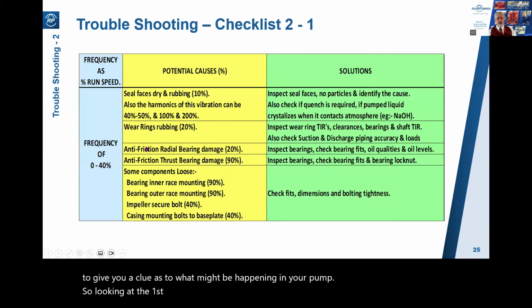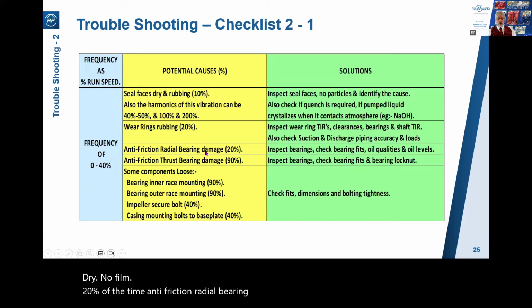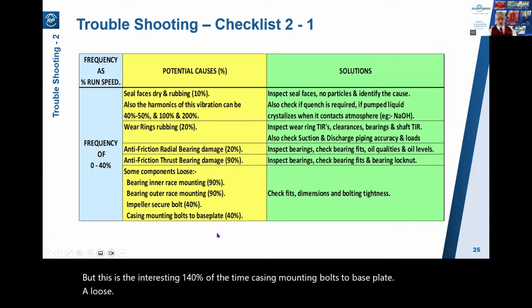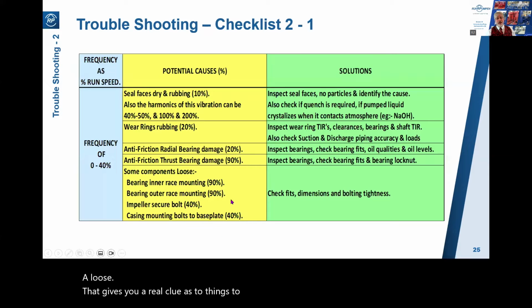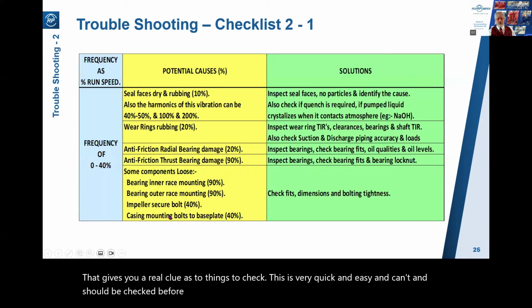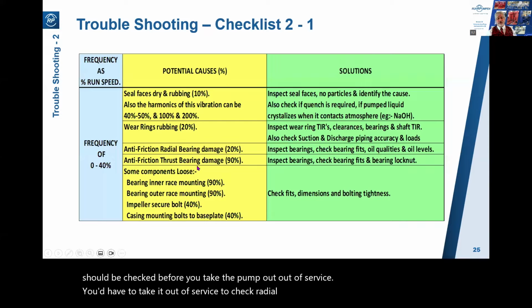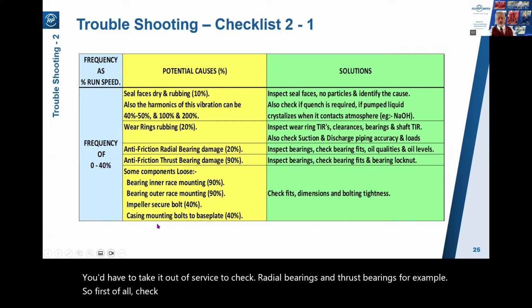So looking at the first slide, vibration frequencies of 0 to 40% of running speed. Well, 10% of the time, seal face is rubbing. They're dry, no film. 20% of the time, anti-friction radial bearing damage. 90% of the time, it's thrust bearing damage. But this is the interesting one, 40% of the time, casing mounting bolts to base plate are loose. Well, that gives you a real clue as to things to check. This is very quick and easy and should be checked before you take the pump out of service. You'd have to take it out of service to check radial bearings and thrust bearings, for example. So first of all, check the obvious, check the simple things.